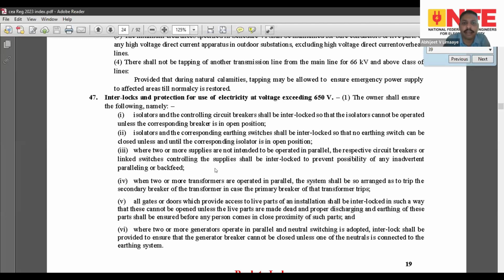You can have a mechanical interlock between them through a mechanism, so that if you are using a breaker, you cannot rack in when the earth switch is on, or in case the breaker is already racked in, you cannot switch on the earth switch. So typically these days it is related more to medium voltage.